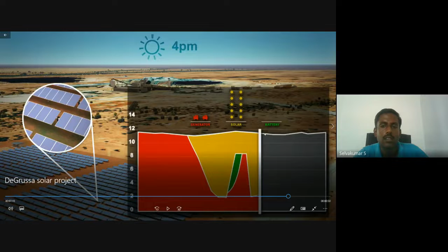And this voltage source converter based bidirectional power electronic device offers synthetic inertia. This is important because solar, being power electronic based, doesn't have inertia. If you compare synchronous machines with inverter-based sources, synchronous machines have inertia, which is missing as far as solar inverters are concerned.